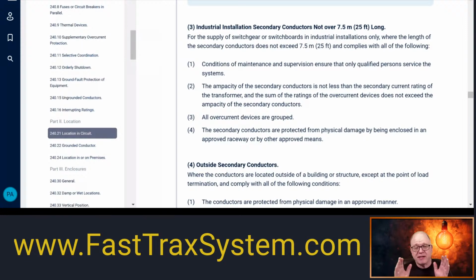Because you're not protecting those conductors. And the whole point is it's similar. That's why it's in 240.21. It's very similar to the tap rules. So you still have your limitations. Now, if you want to, again, come out, what people do is they'll come out of that transformer and hit a single breaker in order to protect it, let's say at that 400, and then they can run it from there any length they want.